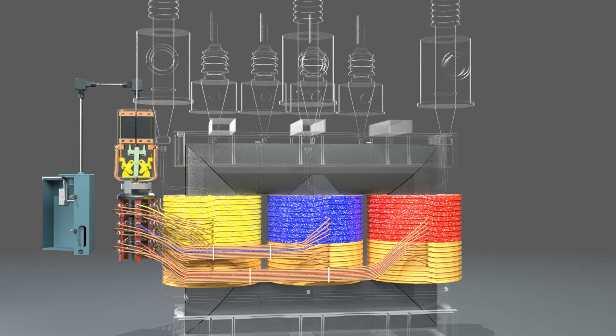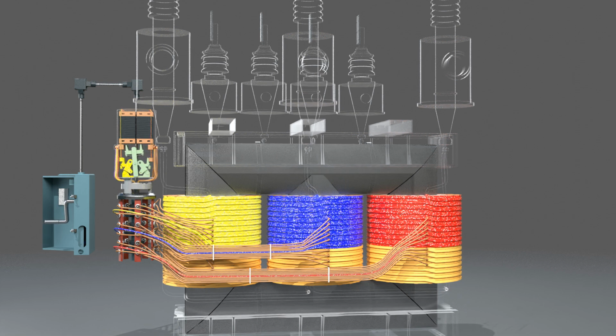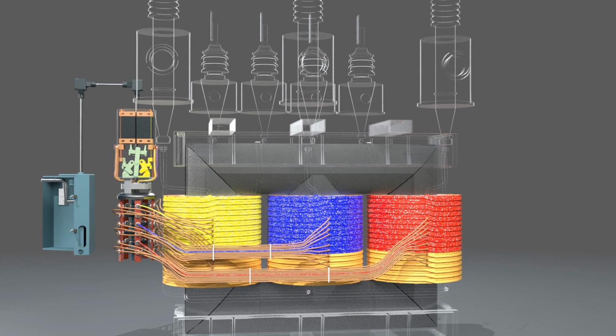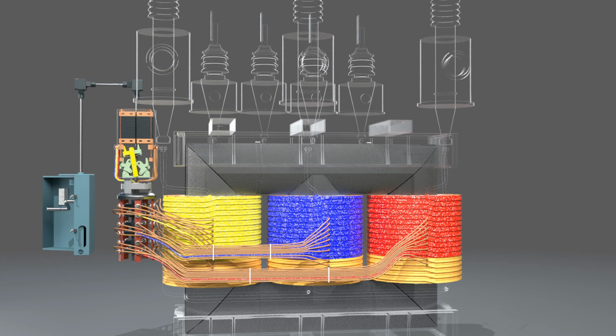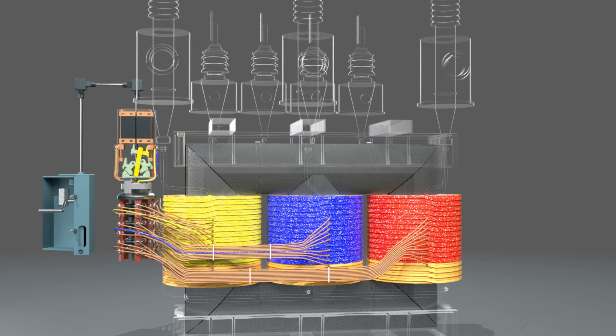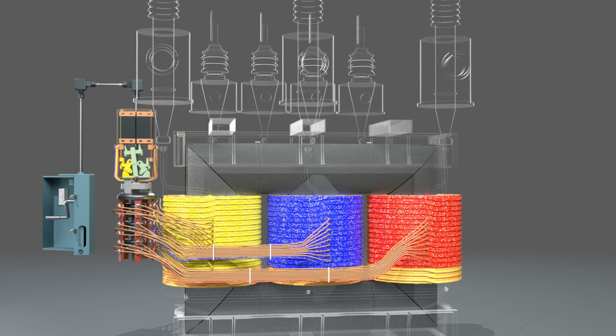When the voltage on the load side is lower than the desired value, the tap changer moves the arm toward a lower tap number on the winding. Lower tap number equals higher turns in the secondary winding, more turns equals higher voltage output. By increasing the number of active turns on the secondary winding, the transformer effectively steps up the voltage to meet the required level.